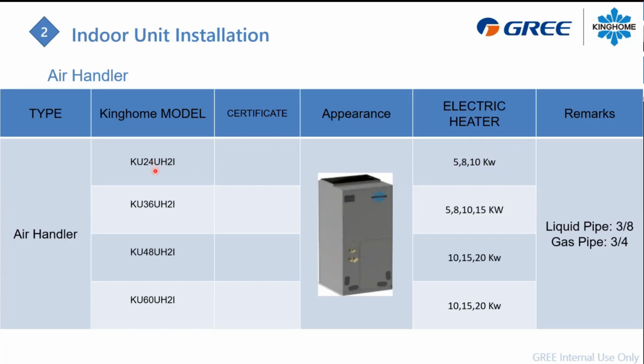Regarding if you have a 2 ton air handler, you will have a 5, 8, or 10 kilowatt compatible. You cannot install a bigger than that. But regarding what kind of unit you are installing, you will match the proper duct heater to it. You can also just take a look that every size from 2 ton to 5 ton, you will use the same piping diameter. So the liquid line will always be 3/8, and the gas pipe will always be a 3/4 pipeline for the refrigerant.